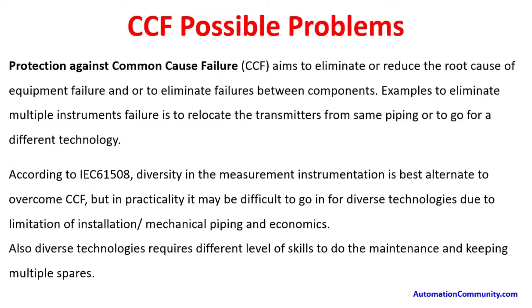Working on any one transmitter may cause disturbance to the second transmitter and can lead to tripping. According to IEC 61508, diversity in the measurement instrumentation is the best alternative to overcome common cause failure. But in practicality, it may be difficult to go for diverse technologies due to limitations of installation, mechanical piping, and economics.